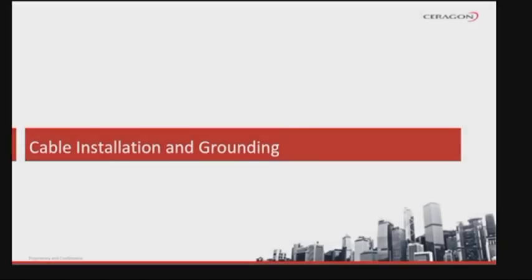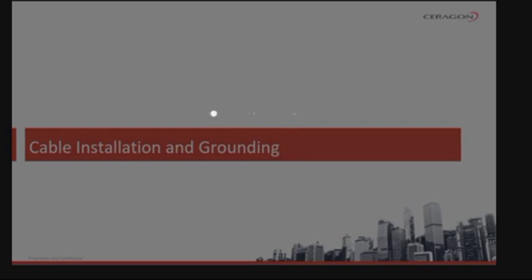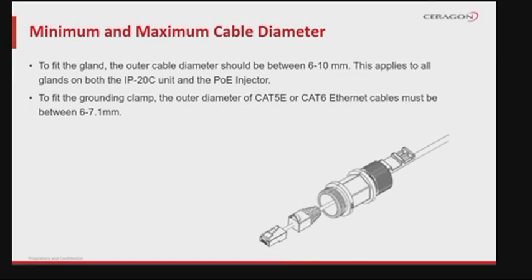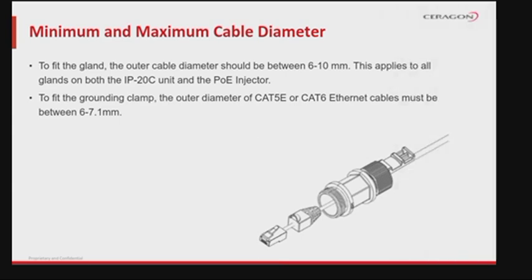Let's talk about the cable installation and grounding procedures. When choosing whatever type of cable for IP20C connectivity, the outer diameter of the cable should stay between 6 to 10 millimeters. This applies to all glands on both the IP20C unit and the PoE injector. To fit the grounding clamp, the outer diameter of a Cat5 or Cat6e Ethernet cable must be between 6 to 7.1 millimeters.